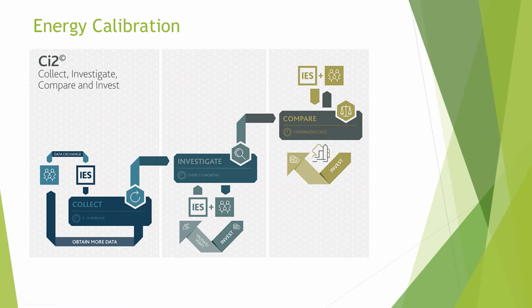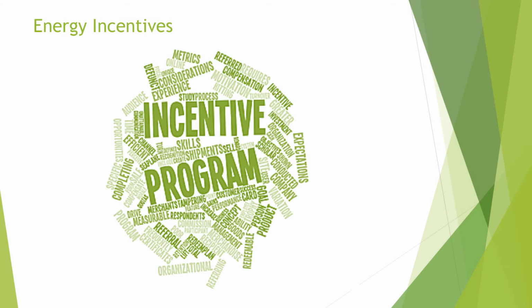Energy models of your existing buildings can be calibrated to actual energy consumption. Meter the energy use, collect this measured data, feed it into the energy model, and calibrate it to match the actual bills. Calibration will help to tune up the building or find errors in operation due to a human factor or system controls faults. There are many government programs to incentivize energy use reduction in existing buildings. Energy modeling can be used to get your hands on this free money to spend on your building retrofits. We can study your building, identify the most desirable and economically feasible options, and help you fund building improvements of your choice.